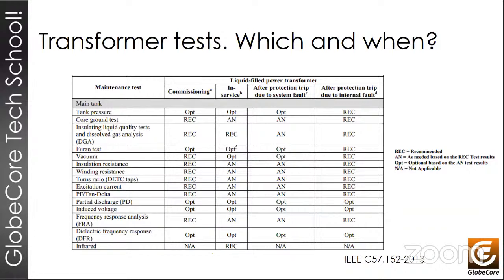There are 4 levels of these possible tests. Some tests are recommended. Some are performed as needed according to the results of the recommended tests. There are optional tests, depending on the results of the previous ones. And there are those that just don't apply. So for example, infrared thermography will most likely not be applicable to transformers that are being commissioned because this transformer is not energized yet. Or after an external or internal fault has occurred, we don't do that because the transformer is probably still disconnected. So these tests won't matter. But they're very important when the transformer is on and running.